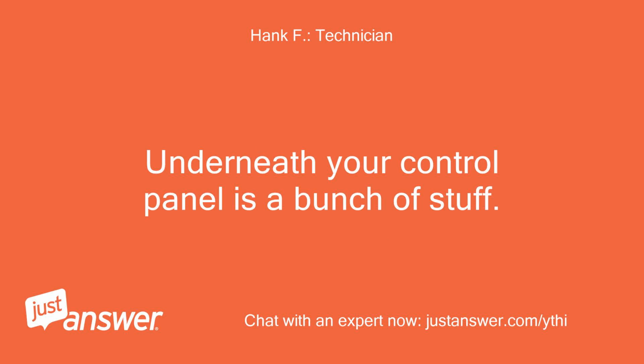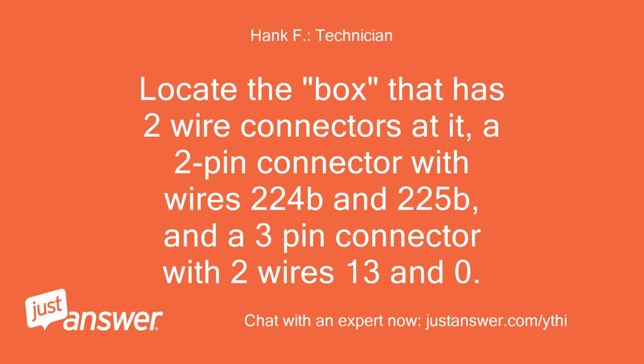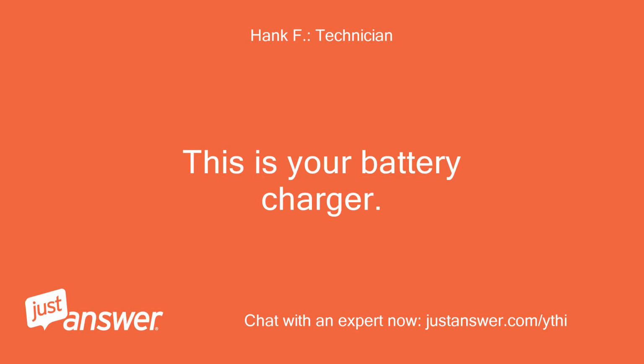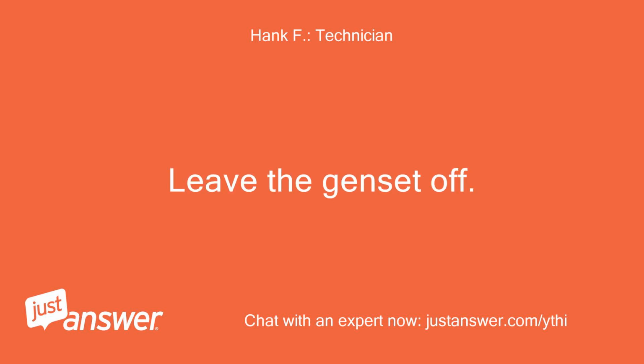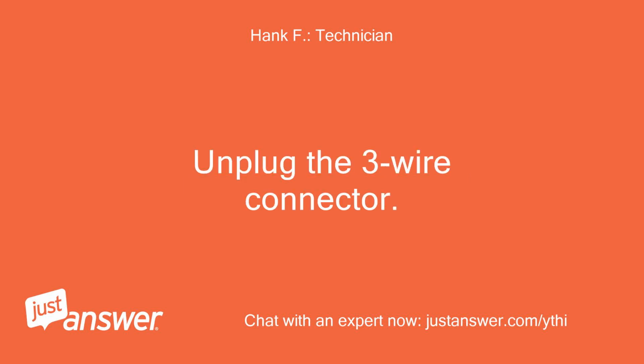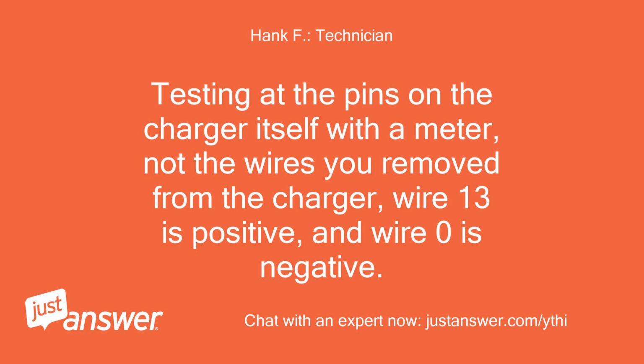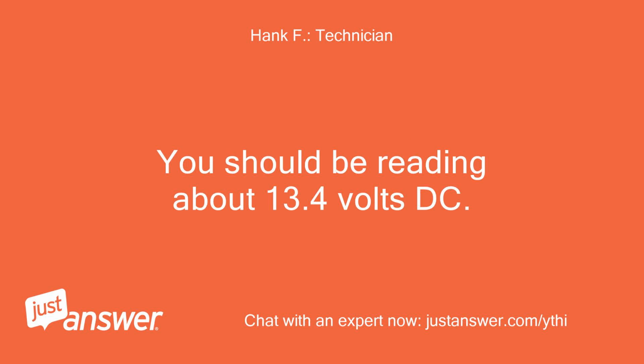Underneath your control panel is a bunch of stuff. Locate the box that has 2 wire connectors at it, a 2-pin connector with wires 224B and 225B, and a 3-pin connector with 2 wires 13 and 0. This is your battery charger. Leave the genset off. Unplug the 3-wire connector. Testing at the pins on the charger itself with a meter, not the wires you removed from the charger. Wire 13 is positive, and wire 0 is negative. You should be reading about 13.4 volts DC.